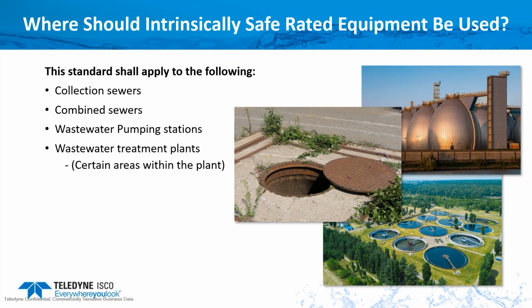So, you know, an area could be declassified if things change where there's adequate ventilation through an area. It's not very often you see a site declassified, but possibly if some walls were removed and there's a lot of airflow through there, that could happen. But you still want to err on the side of caution by getting intrinsically safe equipment.